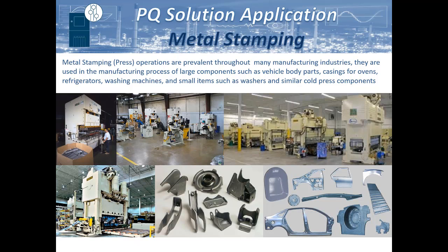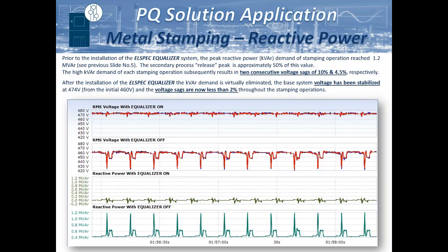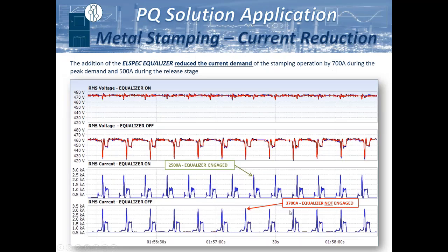There are some industries that we're very well known in, one of which is the automotive industry: metal stamping, plastics, extrusion, things of that nature. The reason is the volatility of the processes. Also lumber mills, injection molding, sawmills. This one is a metal stamping operation. Their nominal voltage was about 460, and under load within the stamping process you can see they're reaching about 420 volts. After we compensate, we maintain a very tight bandwidth where the majority of the time it's only a 4-volt variation. It was all attributed to the reactive power demands of that load.